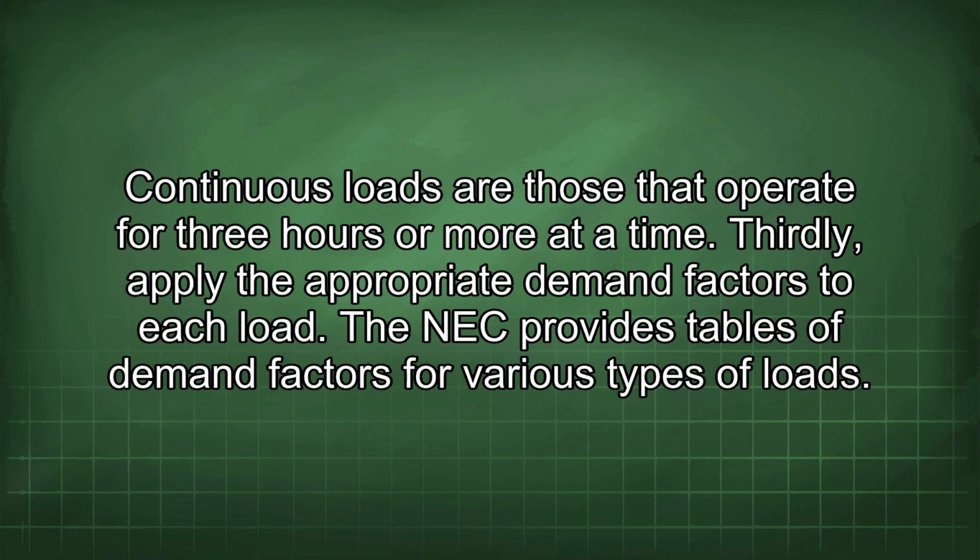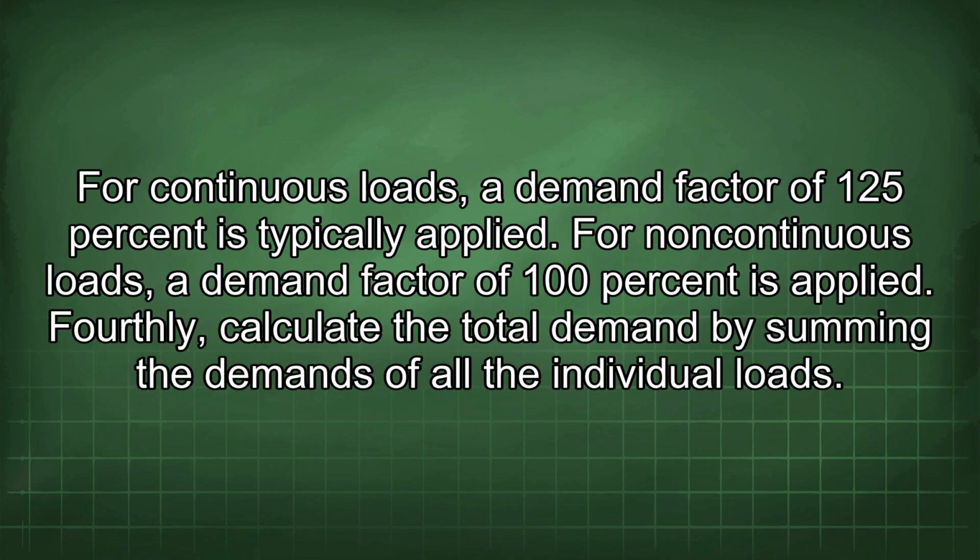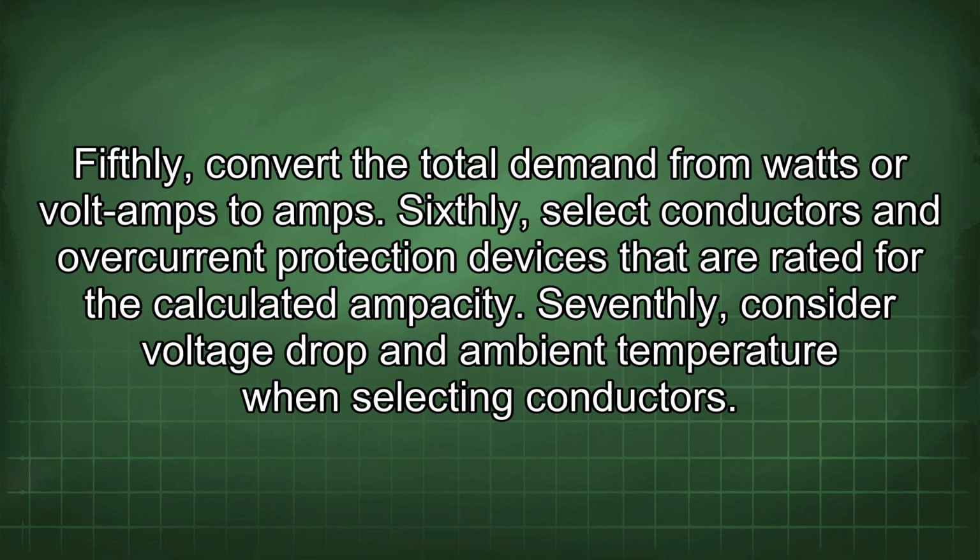The NEC provides tables of demand factors for various types of loads. For continuous loads, a demand factor of 125% is typically applied. For non-continuous loads, a demand factor of 100% is applied. Fourthly, calculate the total demand by summing the demands of all the individual loads. Fifthly, convert the total demand from watts or volt amps to amps.